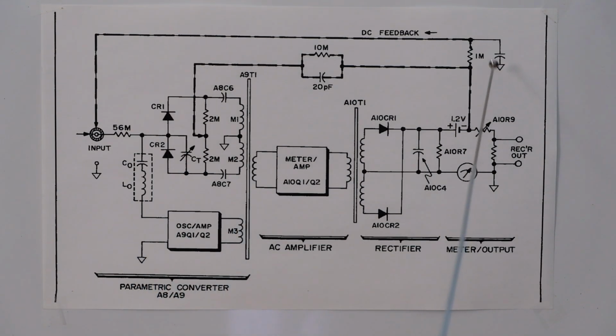And then there is another feedback loop which is used to cancel out any leakage currents that may exist, because when you have a high voltage on the resistor that is being measured, you could have leakage from that resistor into its outer shield to ground basically, or to the cable itself, which then will distort the measurement. So in order to prevent that from happening, they maintain the guard voltage around that cable at the same potential as the measurement. So any leakage is basically cut off into ground. So that's the important part of this particular instrument in trying to measure extremely high resistances.